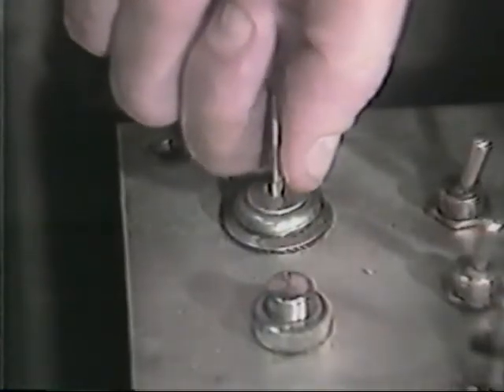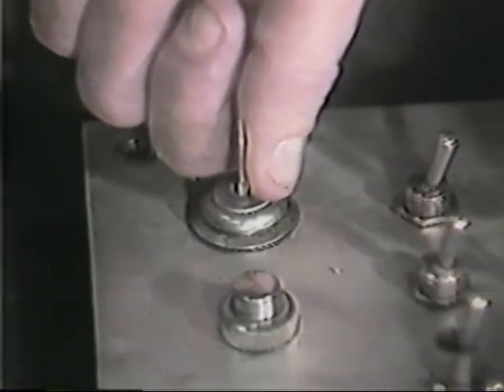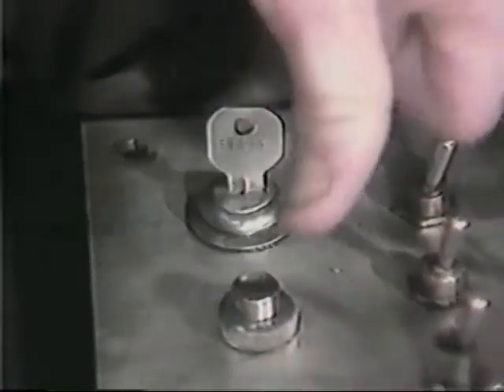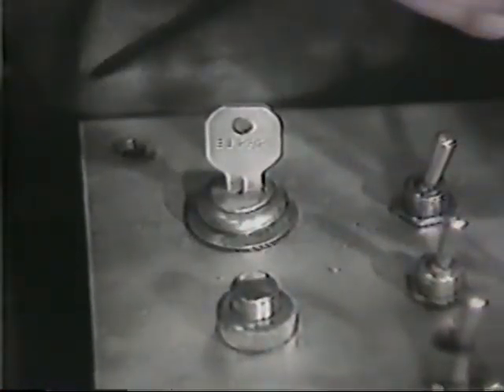The difference in the alarms becomes apparent when the key switch is turned on. There is only a slight beep at this point. If the engine is started right away, there will be another minor beep as oil pressure passes the warning setting of the pressure stat. This feature is called bellhop and is a big favorite with drivers. The alarms come on and stay on only when there is a serious engine problem, not when the key switch is first turned on. Concerning the override, these systems have something called instant on. This means that the module override switch closes as soon as the key switch is turned on, supplying voltage to the module override terminal, the white wire, past the alarm stat NC terminal, and to the fuel shutoff.